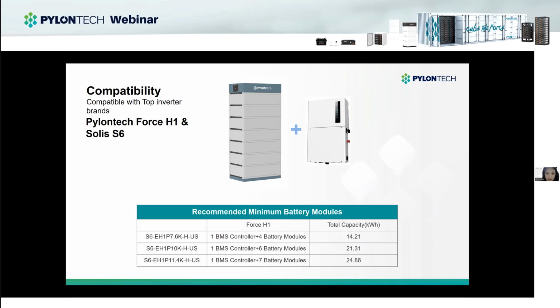The capacity would be 14 kilowatt hour. And if you want to use more battery modules, it's okay, because the inverters and the batteries build the communication, and the battery could always work at 0.5C. Our BMS could protect the battery. And if you wish, you could add or reduce the battery modules for your specific requirement.